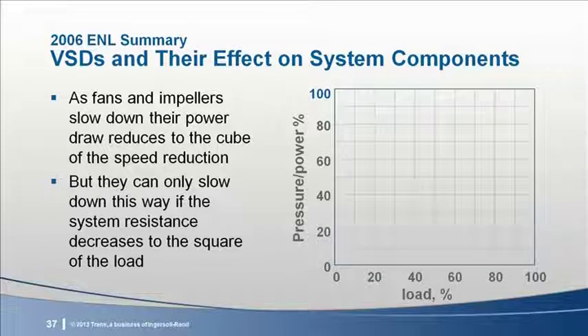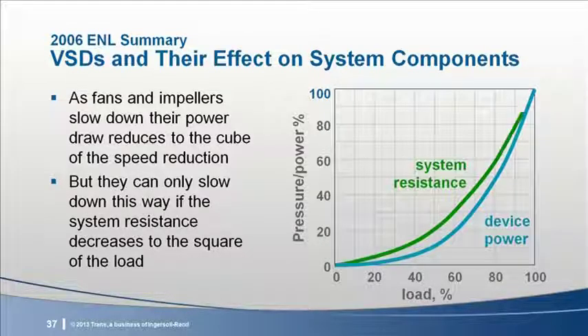First, we all know and love the myth that when you add a VSD to any device, its power use immediately decreases with a cube of the load reduction. The reason it's a myth is that most people use the word load as synonymous with speed and assume it makes no difference. But there is a big difference. The load on the device has two factors, the mass flow and the pressure rise. The only time a variable speed device's power use will fall with the cube of the component's load is if the pressure across the device falls to the square of the load. Very few applications follow this principle of operation.